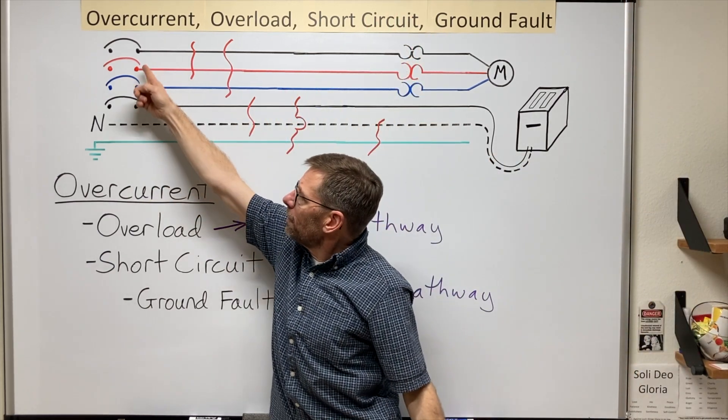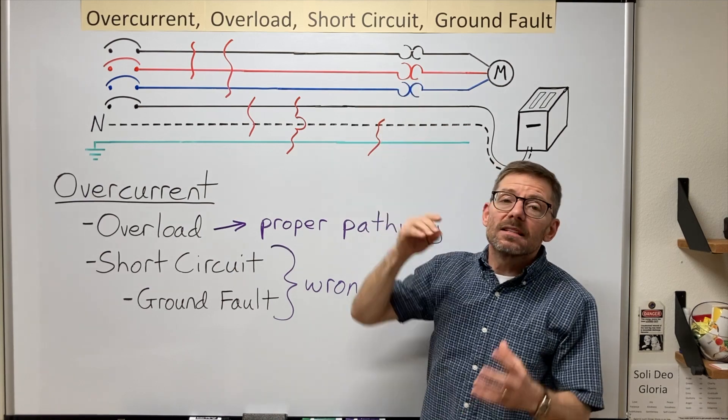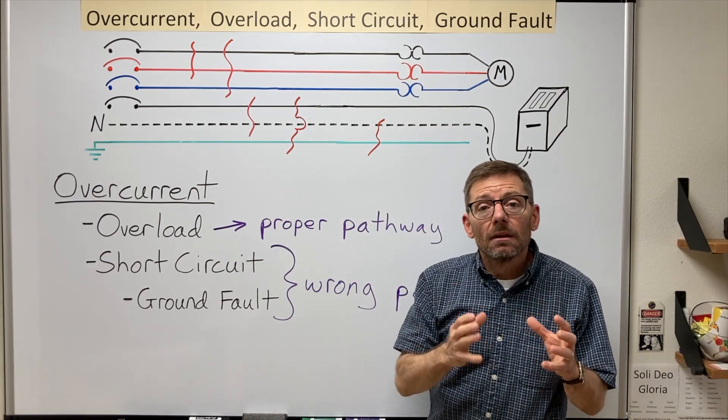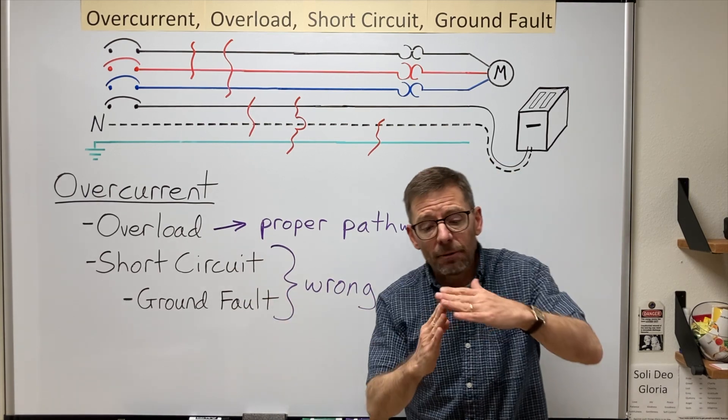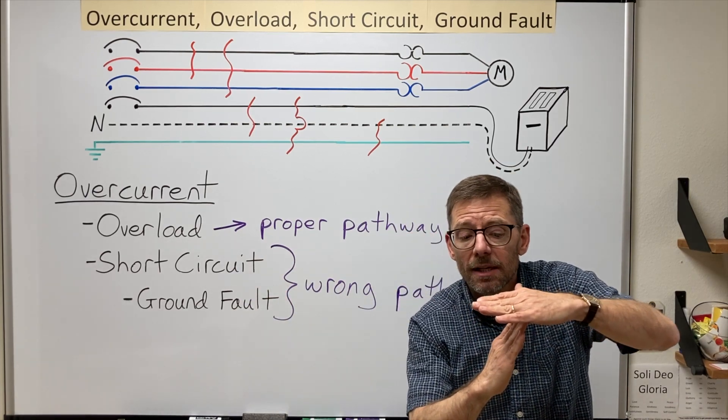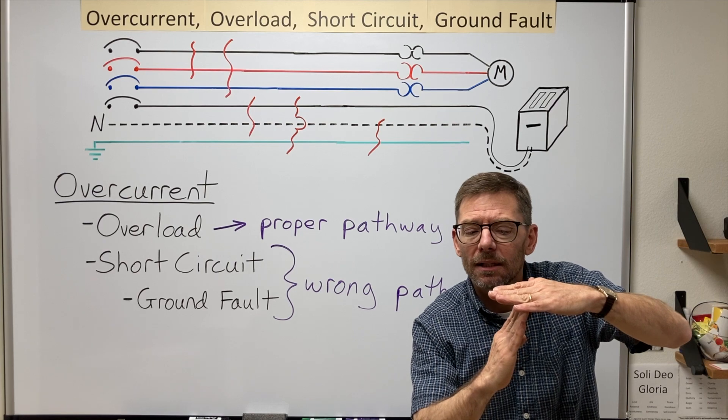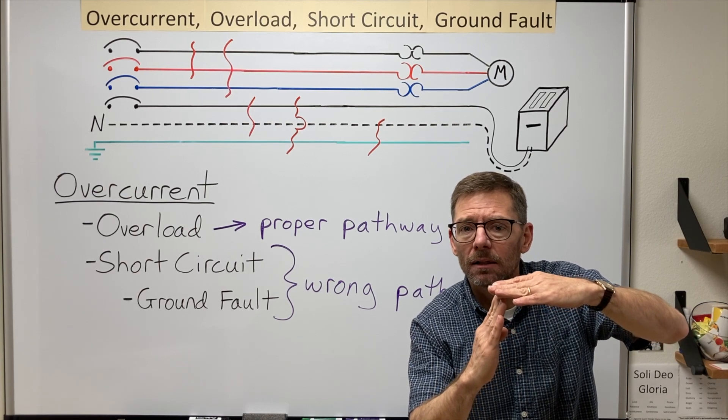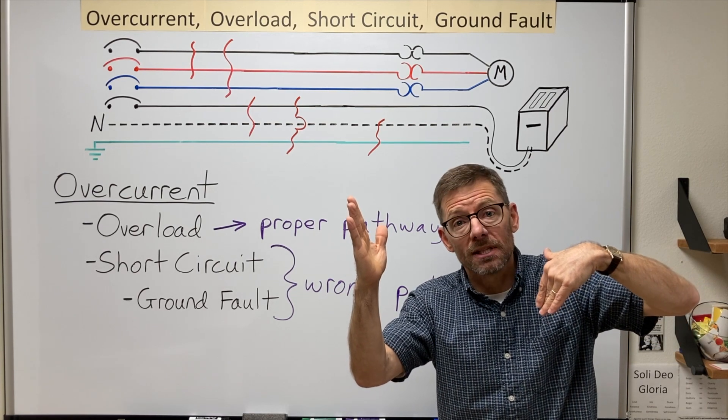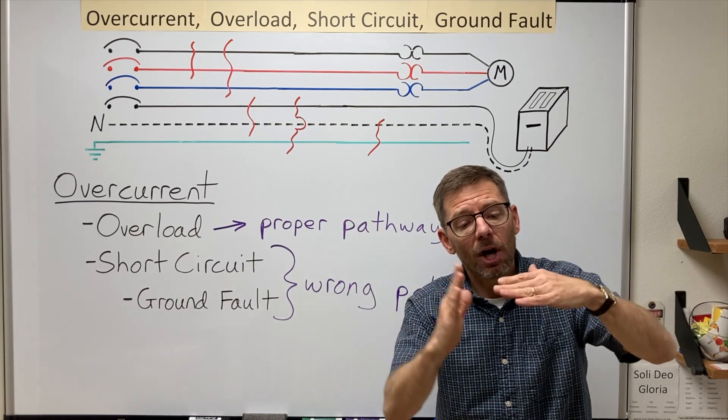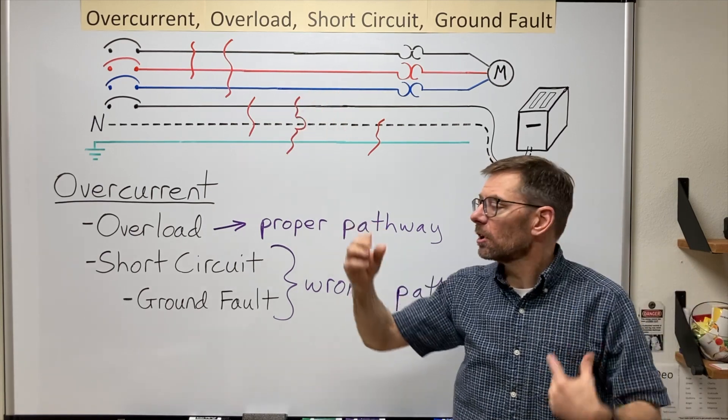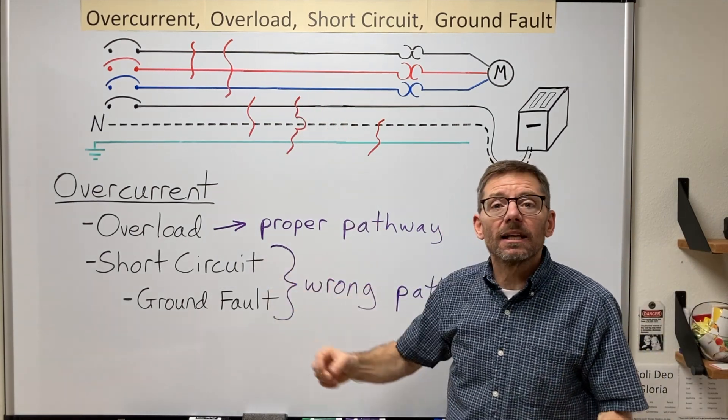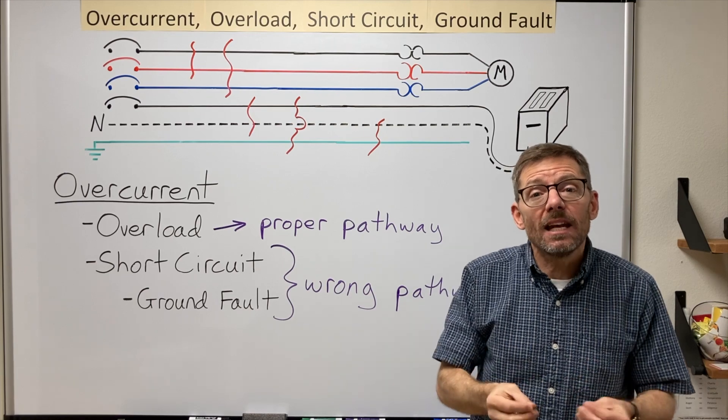So these pieces of equipment are designed to distinguish between overloads and short circuits. For some of them, generally overloads, they'll allow a little extra current for a little while, and then open the circuit before things get too hot. But for others, generally short circuits, they'll open right away, because the current can be so high that it can do damage almost instantaneously.